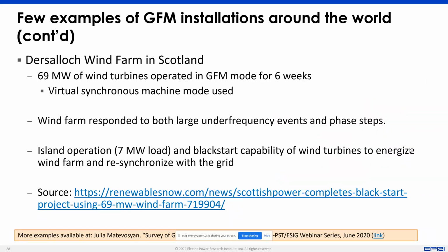There is a wind farm in Scotland which has been looking at doing black start with wind, essentially trying to understand if you have grid forming capability in wind energy systems. Can you do black start? Can you really energize a cable? Can you energize the diesel generator, which is located further away from there? Can you energize the load, and so on?